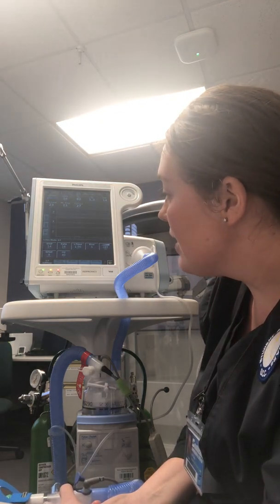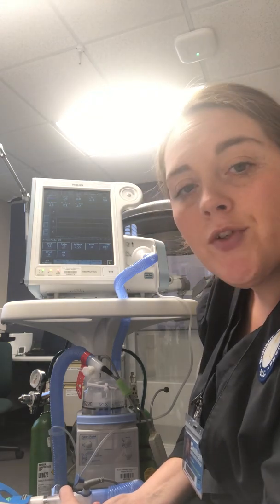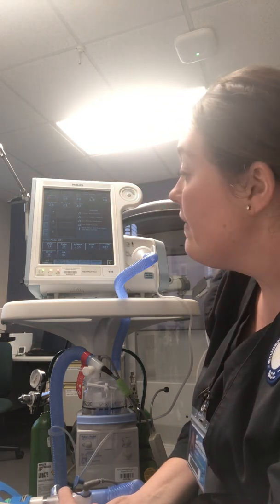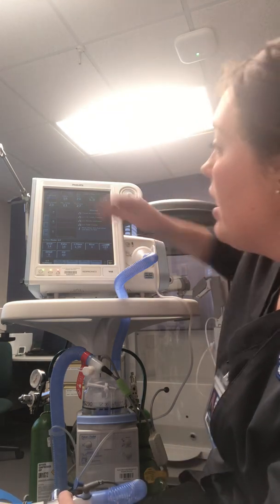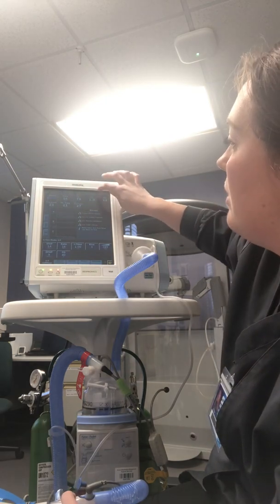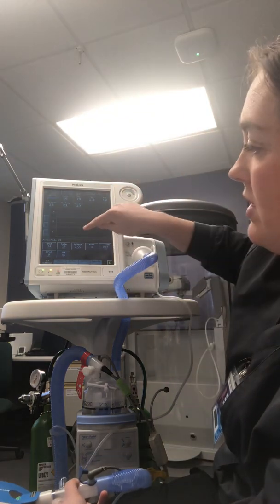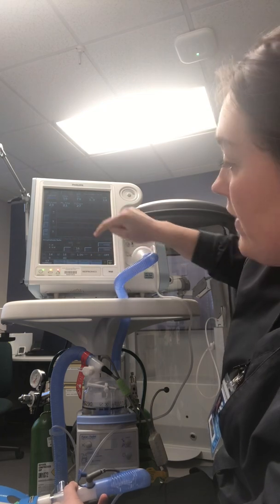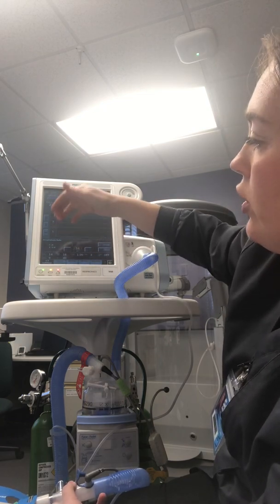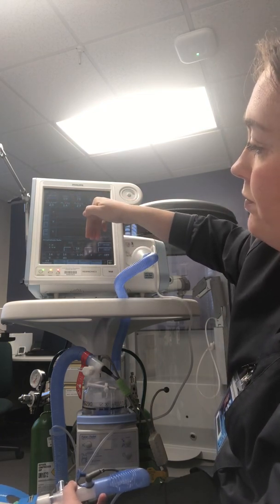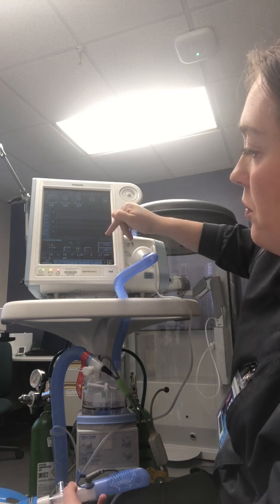We also have the rise time. The ramp is used for patient comfort, and that is how quickly they will get to the IPAP. And then we have our oxygen. So on this type of system, the oxygen can be room air, 21%, or it can be all the way up to 100% oxygen. So to change any of these settings, all you do is click them, and then you can see there's an arrow up or down. You choose how you want that to be, and then you push accept.